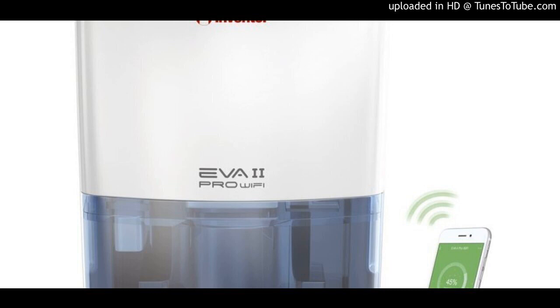To check this, turn on the unit for 30 minutes and then, using a flashlight, examine the front edge of the unit from below. Small water droplets in this area indicate an air seepage problem. Use insulating foam to stop warm air from entering the interior of the device.